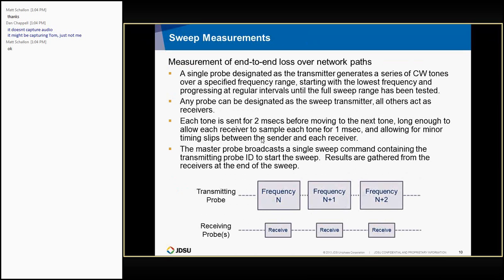Okay, sweep measurements. These are end-to-end sweep measurements where you're trying to measure loss through the network, as opposed to a return loss or a reflected signal. I explain the steps that are involved here. A single probe is designated as the transmitter, not the master. This can be any probe. It generates a series of tones over a specified frequency range, starting with the lowest and progressing at regular intervals until the full range is tested. These sweeps are the ones that run at 2 millisecond intervals. Any probe can be designated as a sweep transmitter. All others act as receivers.